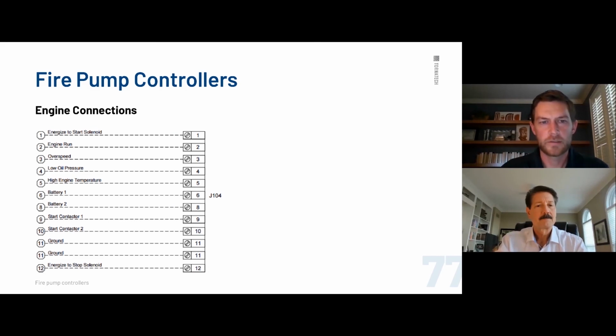Marty, just one note on those. The number 7 wire, obviously, y'all can see there is no number 7 on there. Yes. That is the alternator output current divider. If that's required, we do need to know that. Yes, thank you. Ahead of time. So if you have the number 7 wire, if it's a diesel replacement panel and you have the 7, we need to know that ahead of time. You know, it's an option on the front end, and I'm telling you, it takes a bit of time to install it in the field after the fact. Right. That's a very good point. Thank you so much, Cole. Yep.